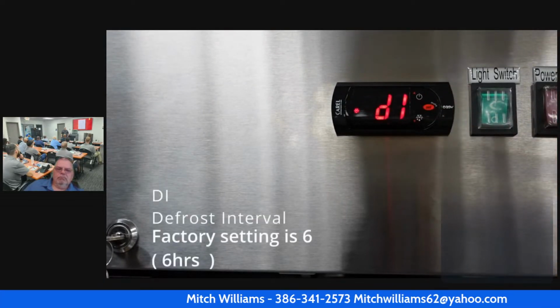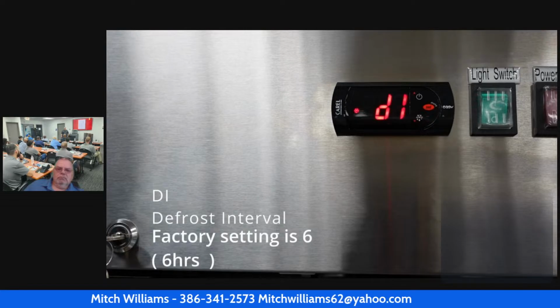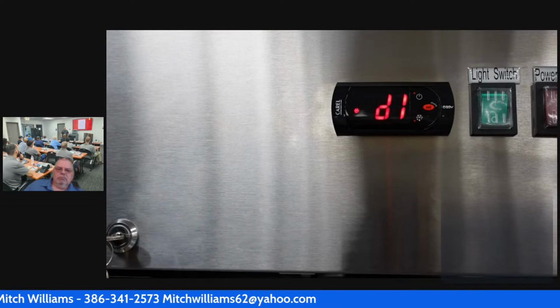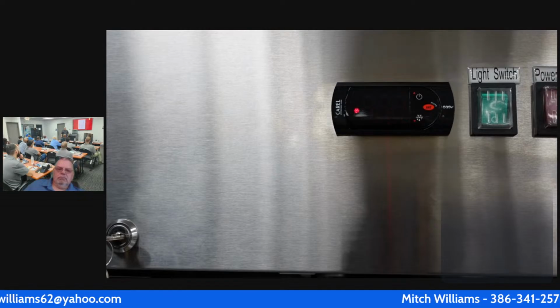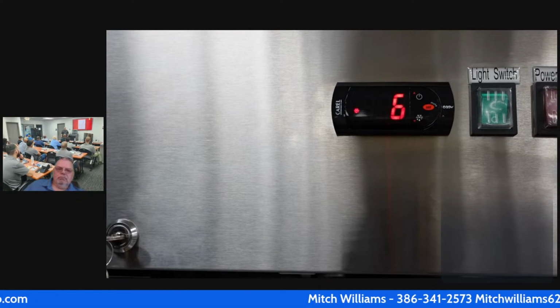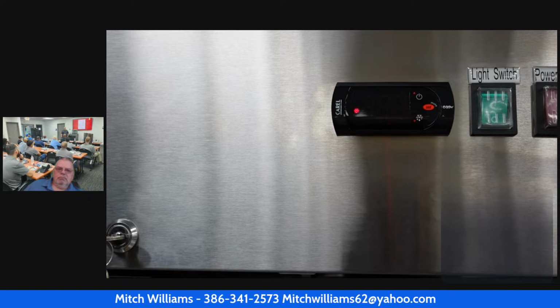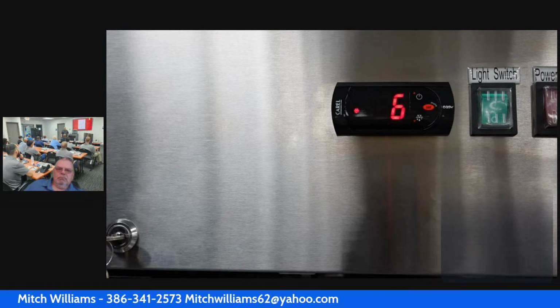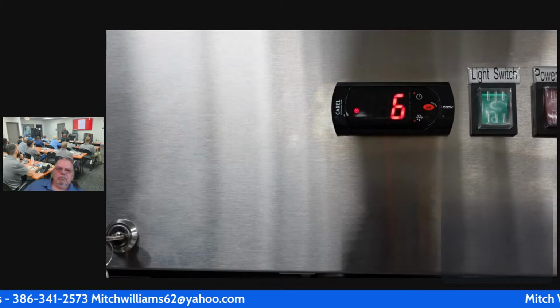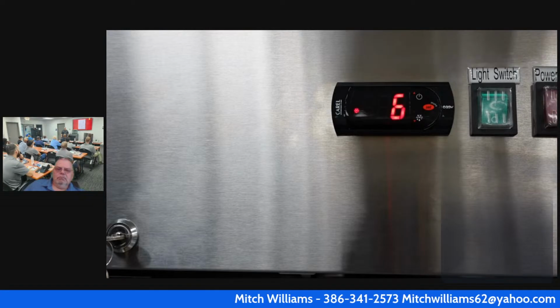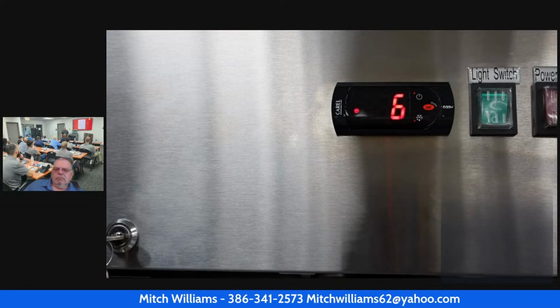The next parameter you'll see is DI. DI is the defrost interval time. The factory setting is 6. This means that the unit is set to go into a defrost every 6 hours. So if DP1 is set to 20 and DI is set to 6, it's going to go into a 20-minute defrost every 6 hours. Adjusting this parameter might result in freeze-ups near the evaporator.